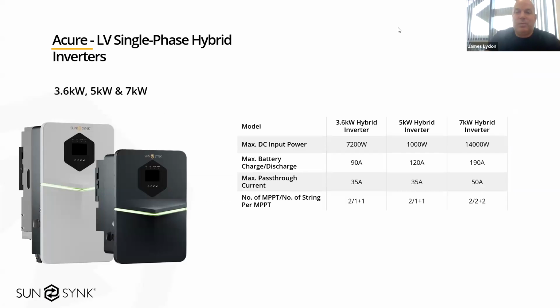Okay, the current range that we have in stock, we've got the 3.6, 5, and 7 kilowatt single phase. As I mentioned, they've all got 100% PV oversizing, as you can see on the table below. And then you've got your max battery charge and discharge current. As I mentioned, when you work it out, 90 amps at typically 50 volts, it's always going to give you the max charge and discharge at the rated value of the inverter.